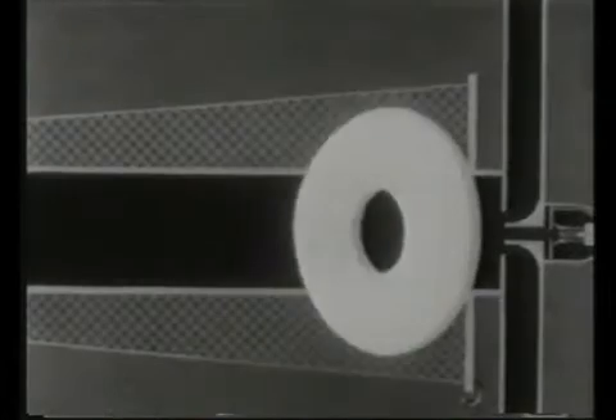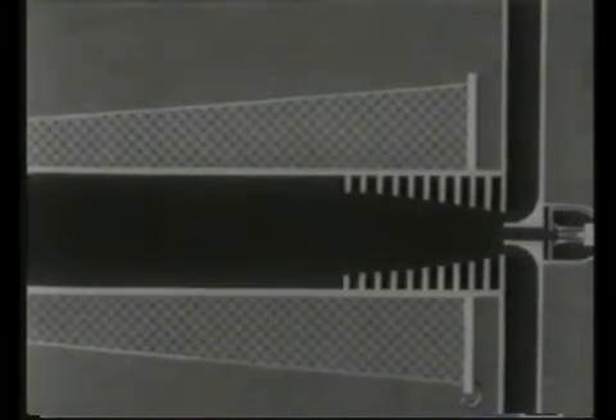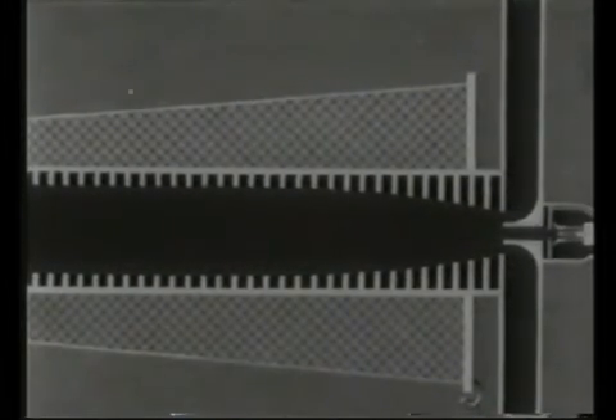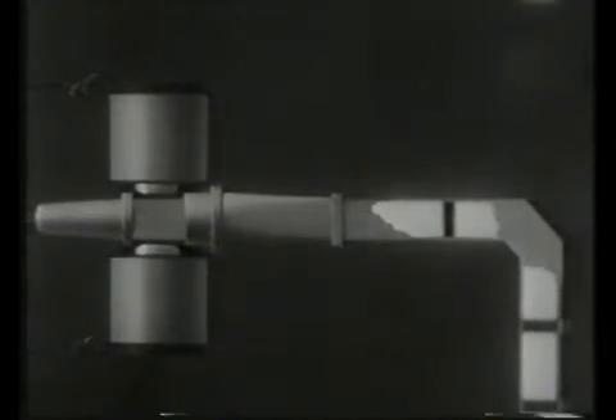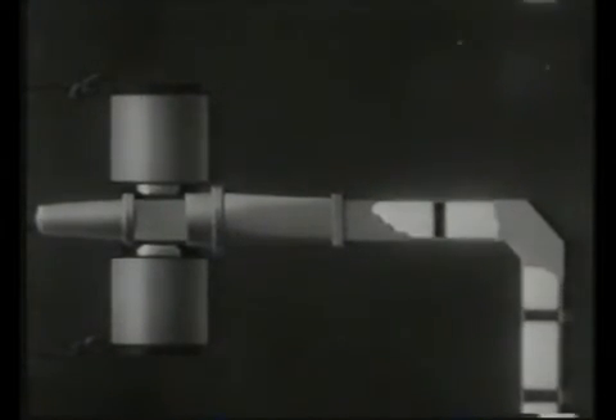Control of wave velocity is achieved by loading the cylindrical waveguide with iris plates. These are spaced at equal intervals along the tube, their apertures increasing towards the target end. The wave in the rectangular waveguide is traveling at a phase velocity of 140% c. On entering the cylindrical waveguide, corrugated by the iris plates, each field of the wave is slowed down to 40% c, which is the injection velocity of the electron.